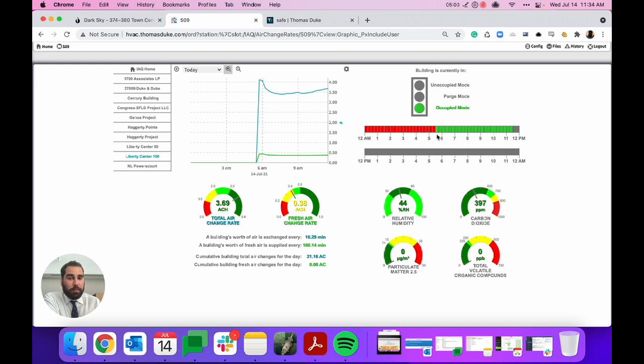Going through here, we have the building schedule. Looks like the equipment turned on at 5:30 a.m. this morning. We're in occupied mode. The building humidity is 44%. Perfect. We actually don't have great control over humidity like we have control over other factors, so we can't target that one. We're not able to increase that like we are the temperature. Carbon dioxide, doing okay.